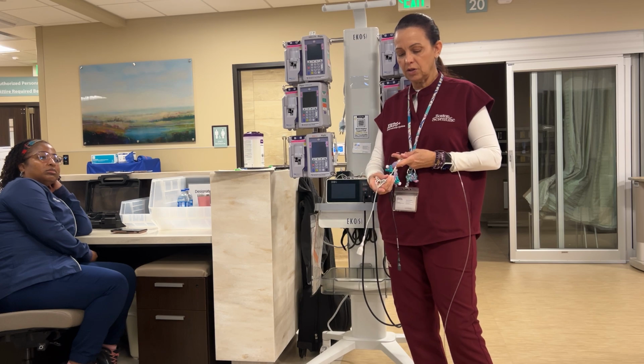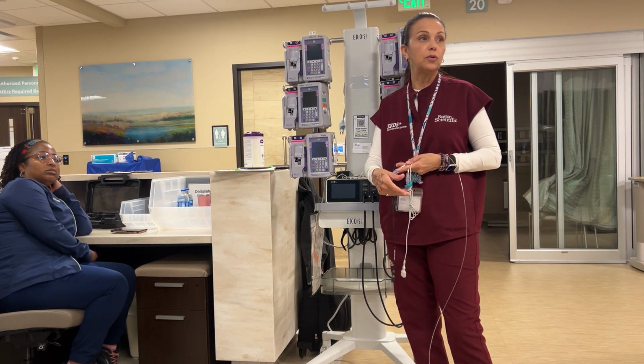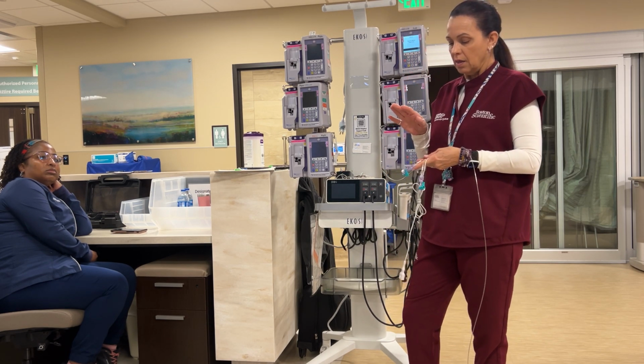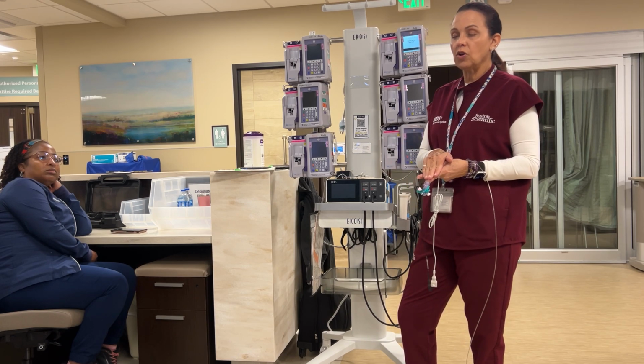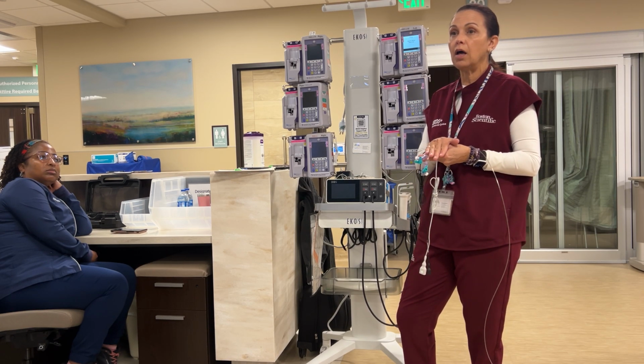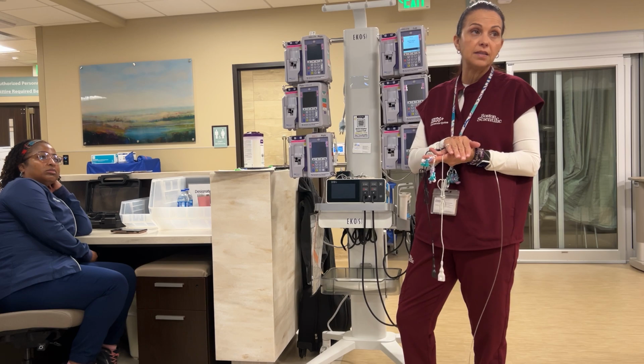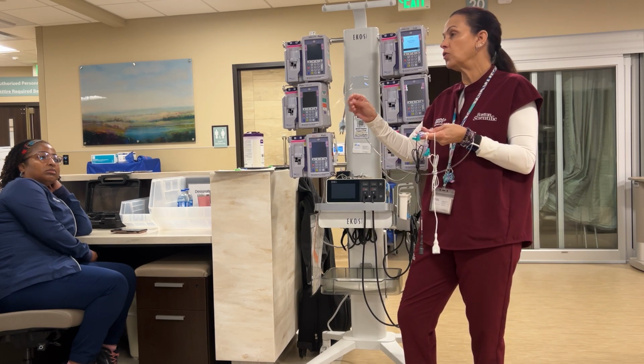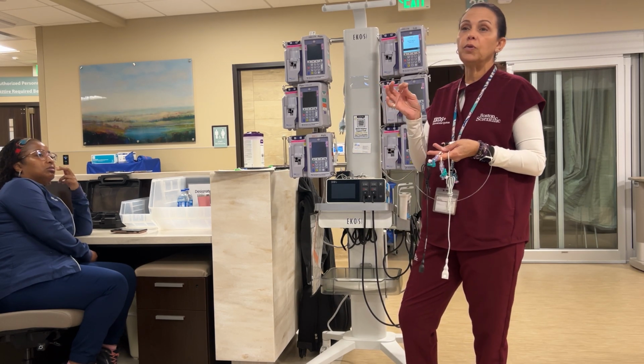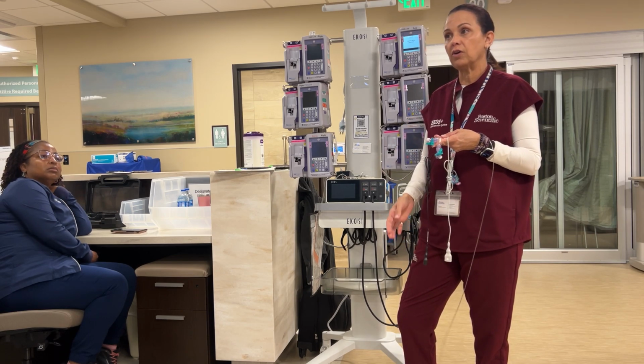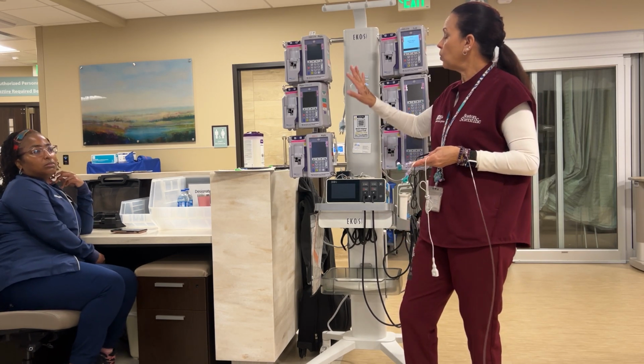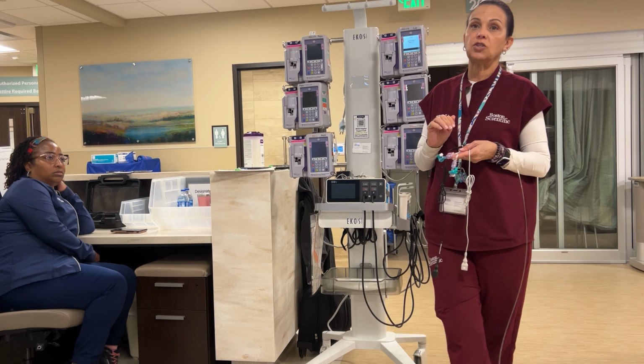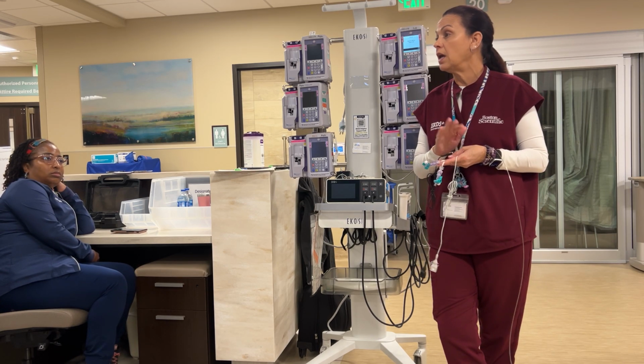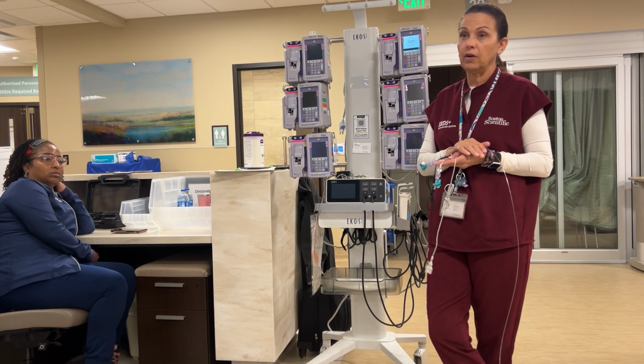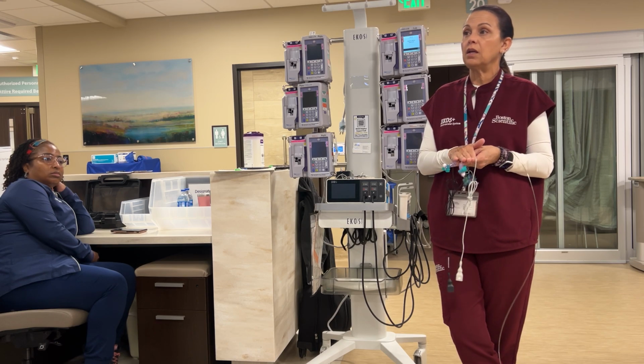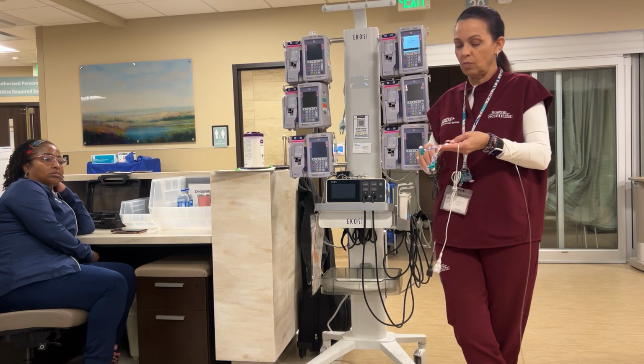So the stopcocks are here so we can make a fluid-to-fluid connection in the cath lab. You never want to draw back on this catheter once it is placed in the body. With the infusion holes being so small, you would effectively clot the catheter off and render it useless. Also, you never want to give any meds other than what's connected to your pumps. You'd be injecting into clot and the medication wouldn't be circulated very well. So forward flush only, never draw back, never give any meds other than what's connected.